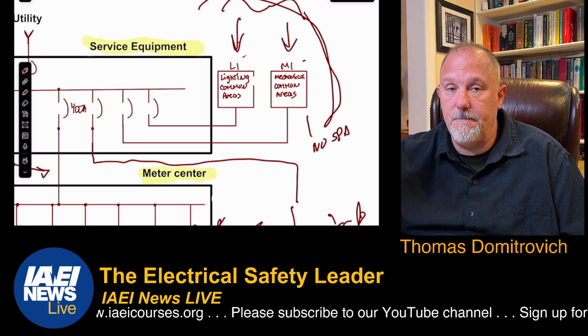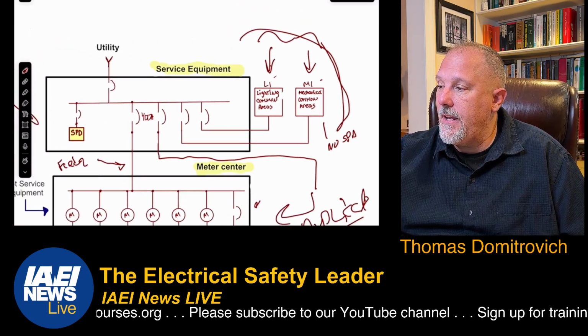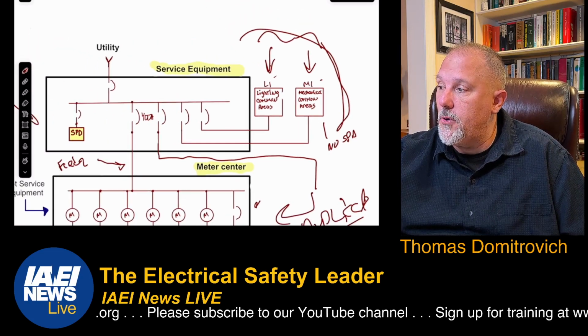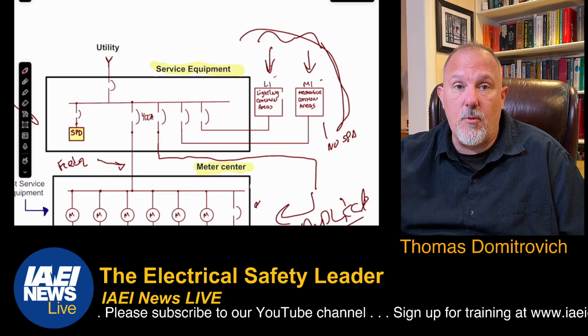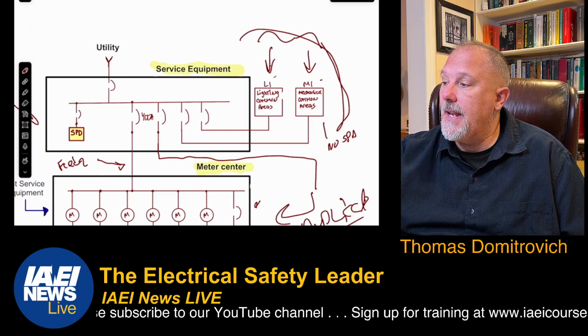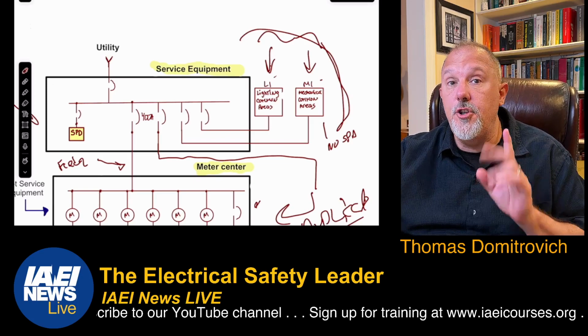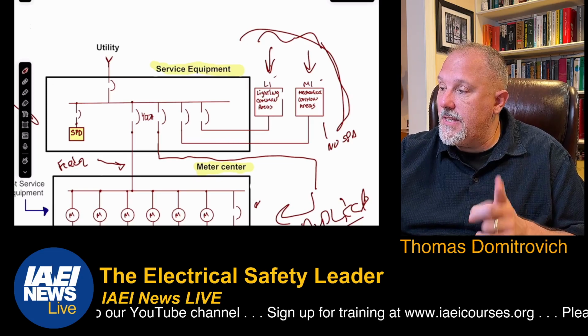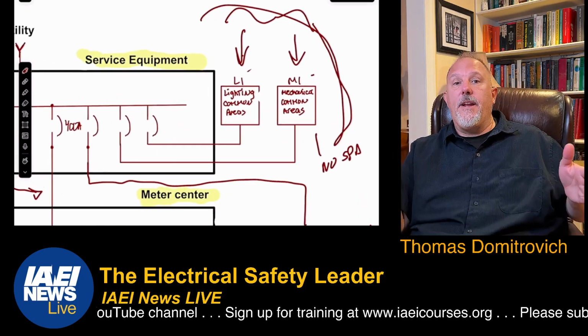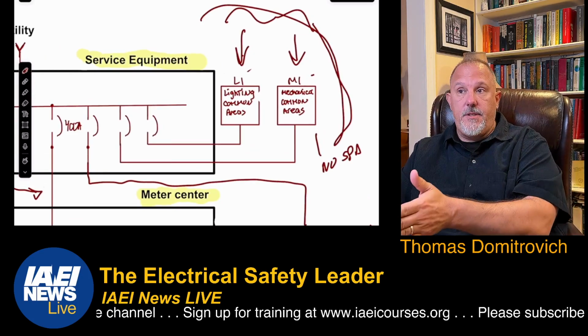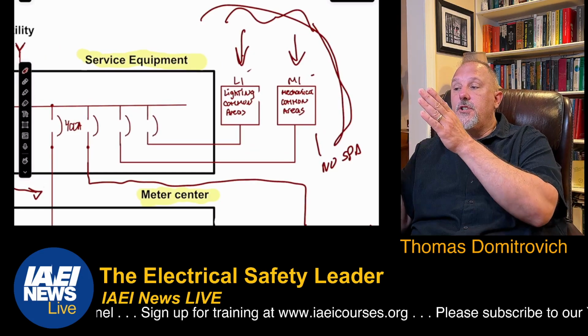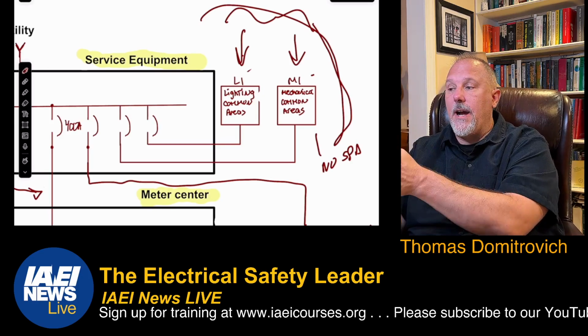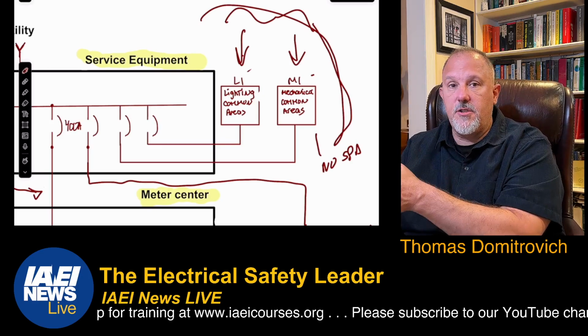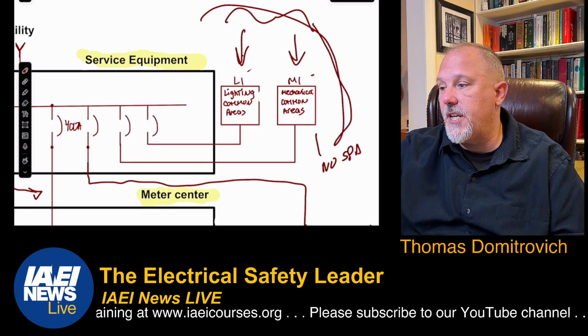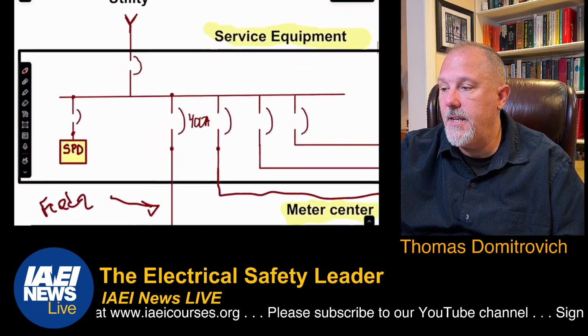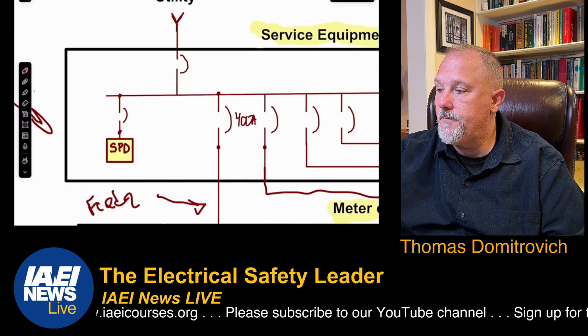each of those distribution pieces of equipment have to have a surge protective device to leverage the exception in 230. If you don't have it in L1, and in fact there were multiple panels, it wasn't just an L1 and M1, there were multiple panels. They elected not to put them at those because there was no requirement, because this equipment fed common areas. It did not feed a dwelling unit. So there was no requirement in the code to require surge protection at those panels. So instead of putting surge protection at those panels, they put it in the service equipment.